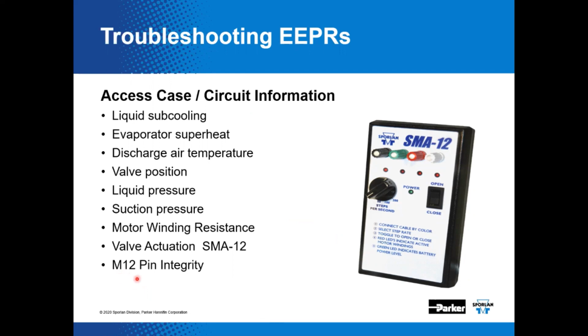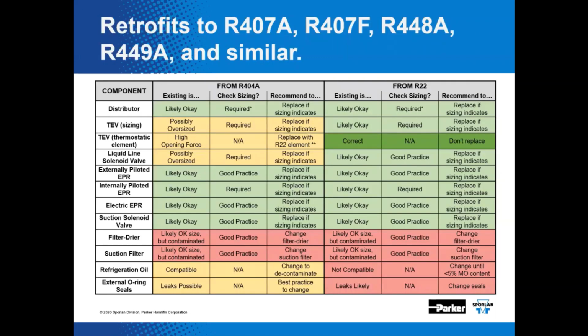Also on the M12 pin, it'd be a good thing to inspect it for integrity and that you haven't bent any pins. And one thing I haven't shown on here is simply an ohm meter. Correct. Checking resistance, checking voltage, all that sort of thing. Yep. That would be an invaluable tool for you to have as well. To be able to know we have the correct resistance across the windings lets you confirm that you have a properly functioning motor.